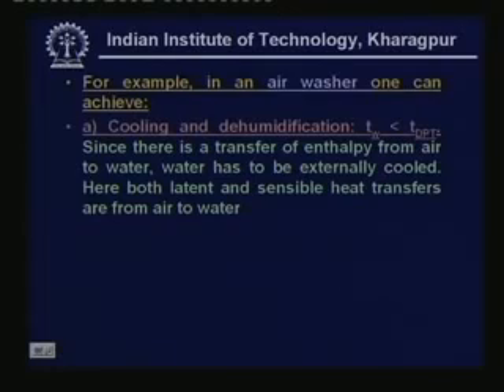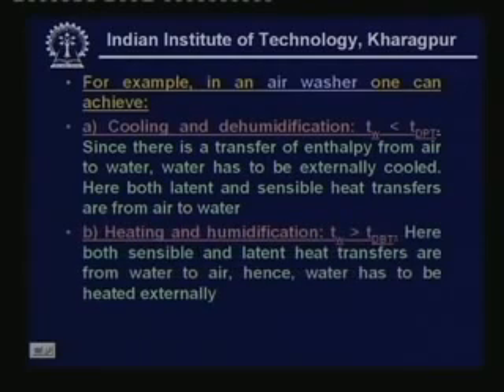Here both latent and sensible heat transfers are from air to water. For the reverse process, heating and humidification, you have to spray water whose temperature is higher than the dry bulb temperature. Here both sensible and latent heat transfers are from water to air, hence water has to be heated externally. In the first case water has to be cooled, in the second case water has to be heated.